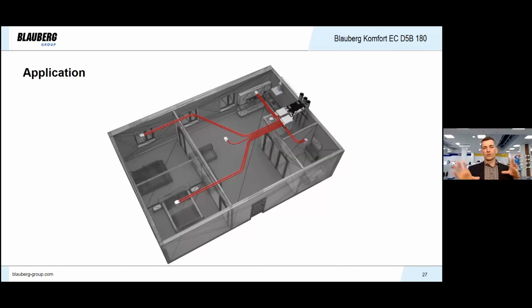I'm sure that you know how this unit is typically applied, but in brief, let me show a typical application where the unit is suspended under the ceiling in a technical room. On this slide you can see an apartment. Let's imagine that this is an apartment in a multi-story building, and the unit is used together with the Blaufast semi-rigid duct system. There are 2 distribution boxes. One distribution box extracts air from the kitchen, utility room and bathroom, and the other distribution box supplies fresh air to the living spaces like bedrooms.